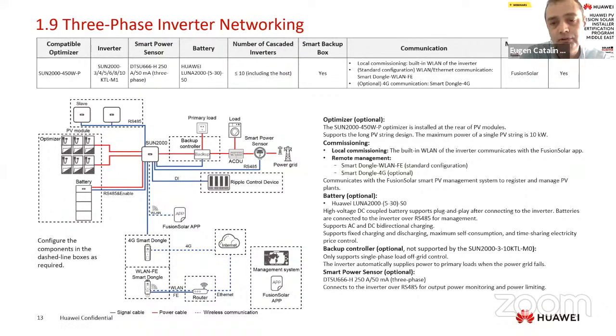The connection to the internet and Fusion Solar will be made through a dongle, of course. The M1 generates a built-in WLAN, but only to connect locally to the inverter to set it up with the Fusion Solar app. And we'll have in the package, as I said before, a Smart Dongle WLAN-FE that will connect the inverter to the internet using Wi-Fi or the Ethernet cable. In a cascading scenario, only the master inverter will have the smart power sensor and dongle, and that's it. The rest of the inverters, which are slaves, will be connected through RS485 communication to the master inverter. We will perform a daisy chain between the slaves and the master inverter.